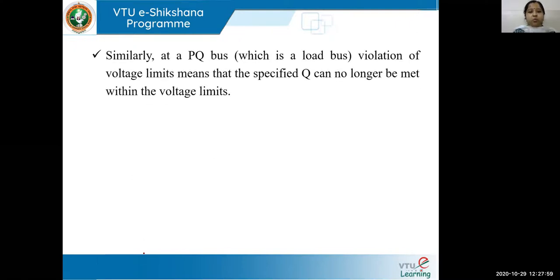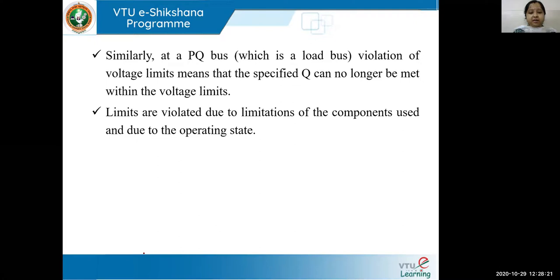At a PQ bus, violation of voltage limits means the specified Q can no longer be met within the voltage limit. The voltages and angles found at PQ buses should remain within specified limits. Limits are violated due to the limitations of the components used and due to the operating state.